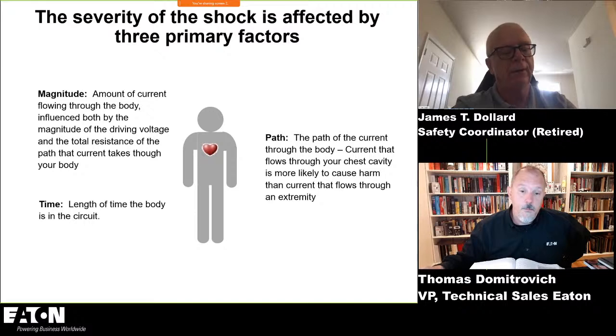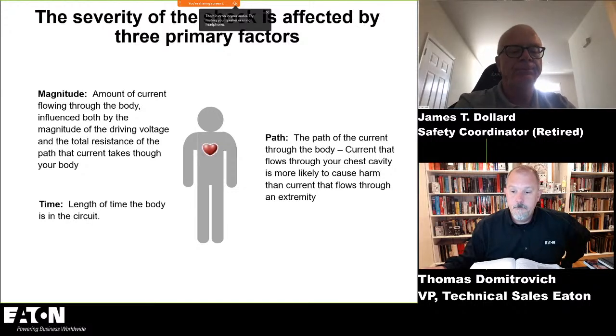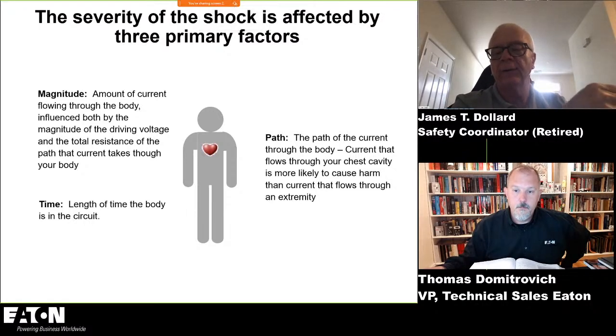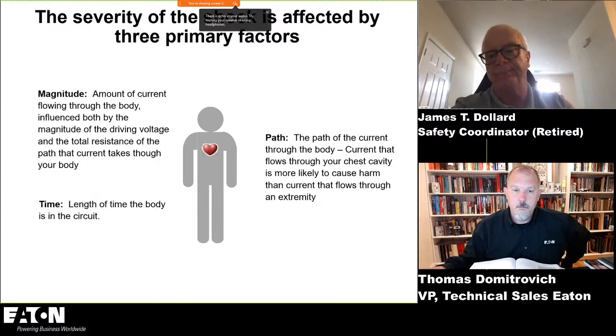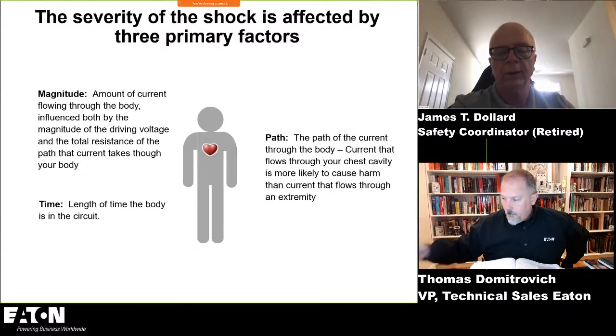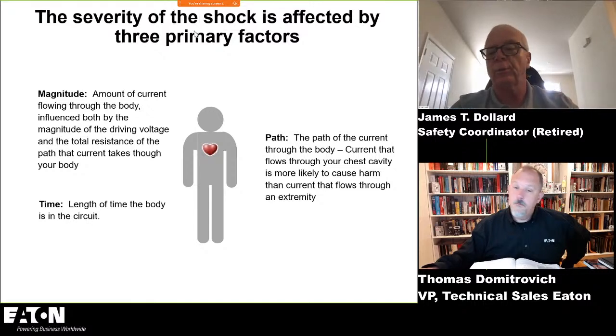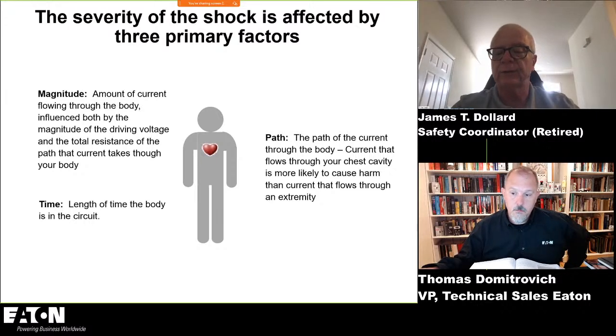Yeah. Well, basically, if you go into Home Depot or Lowe's and you buy a standard GFCI receptacle, and you wire it up and you open the neutral, you can get current flow to ground through that receptacle till the cows come home. It'll never trip because the brain in that device only operates if it sees 120 volts. So a GFCI that is listed as portable, the older ones had a mechanical recloser on it. The new ones, it's just a relay inside the device. So when you're buying those to use around the house, and in construction, for example, you can use a permanent receptacle, but you have to plug in a GFCI device that is listed as portable at the point of use.